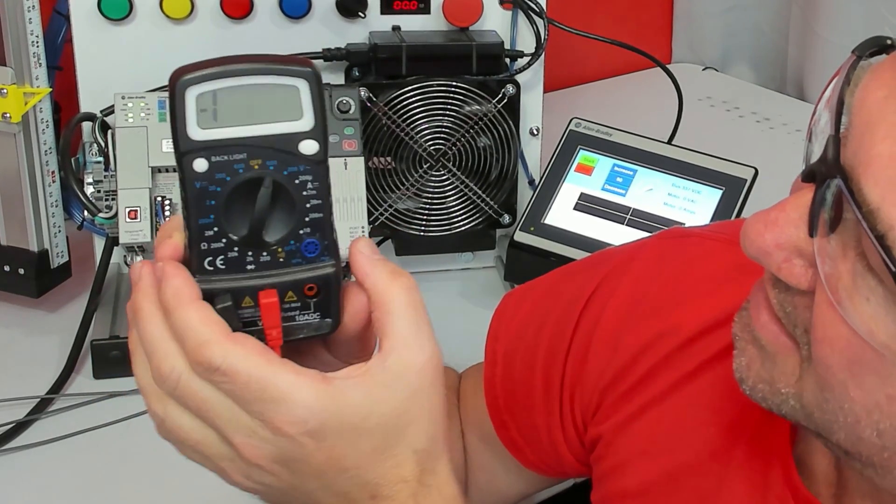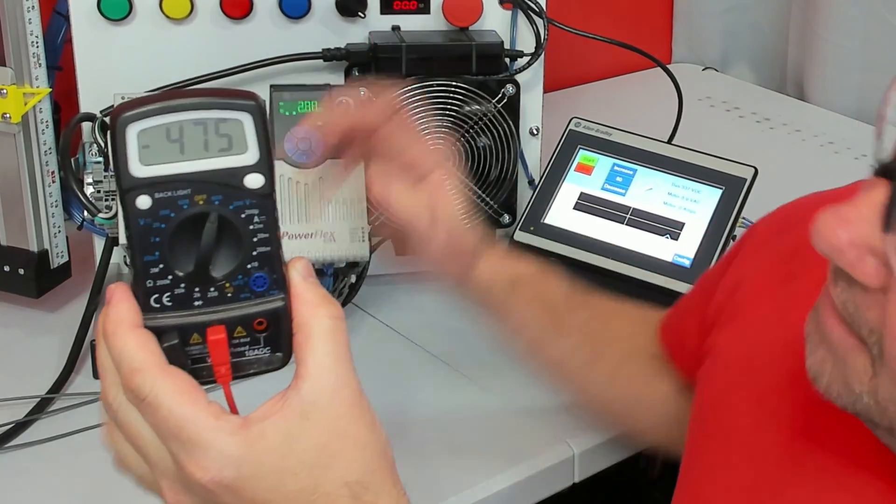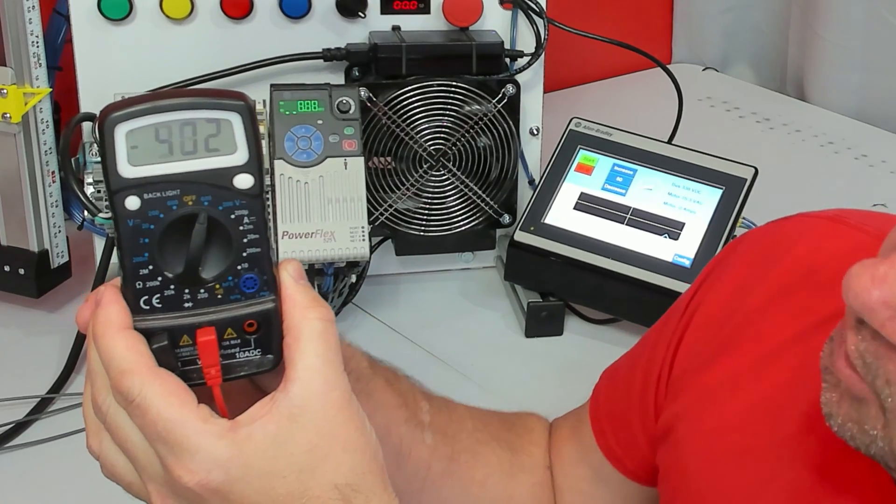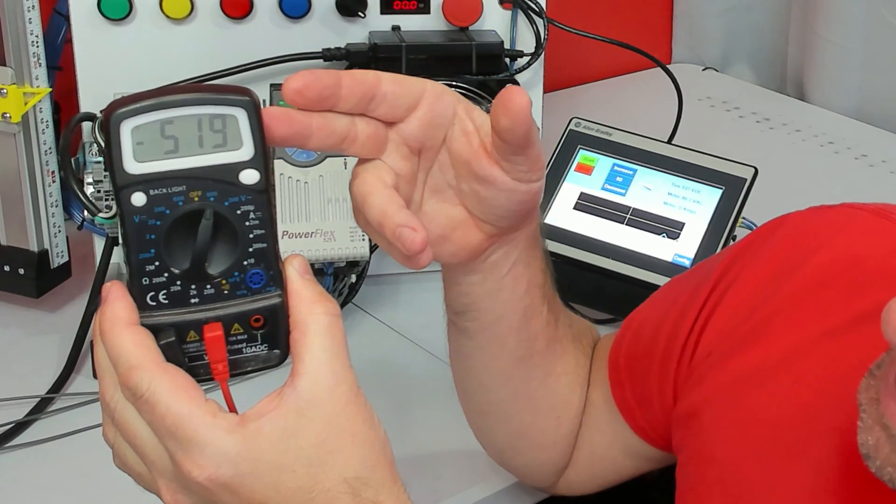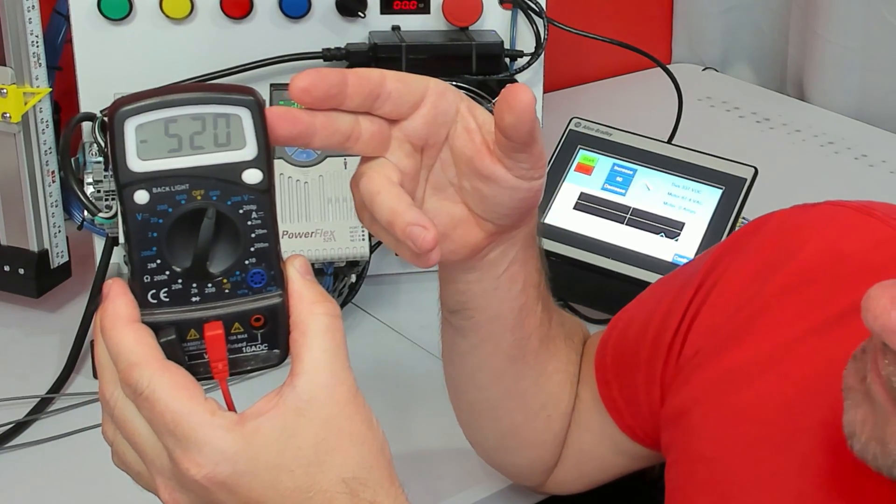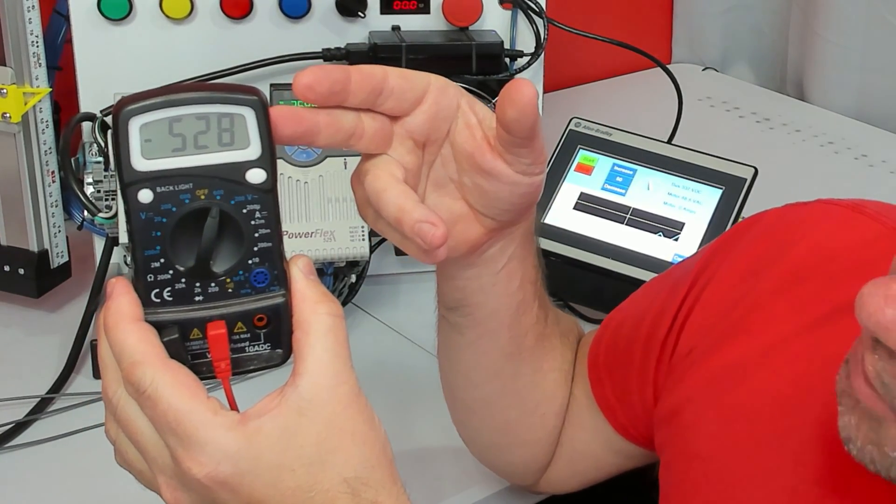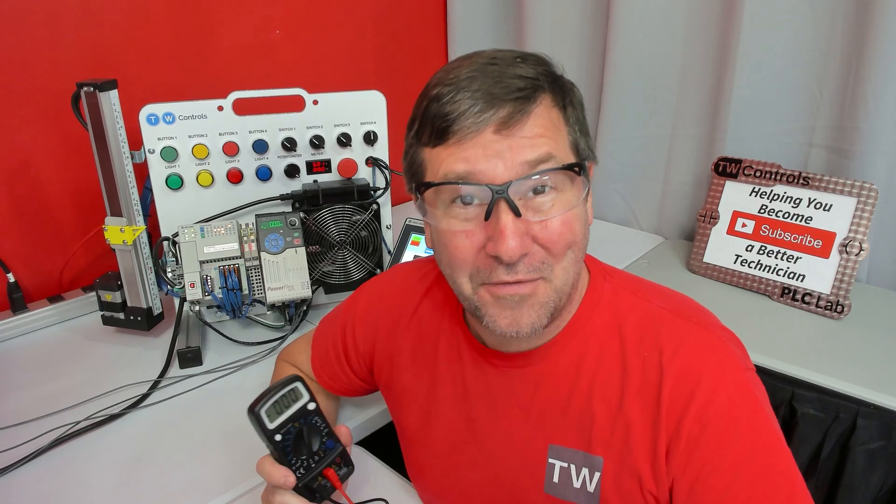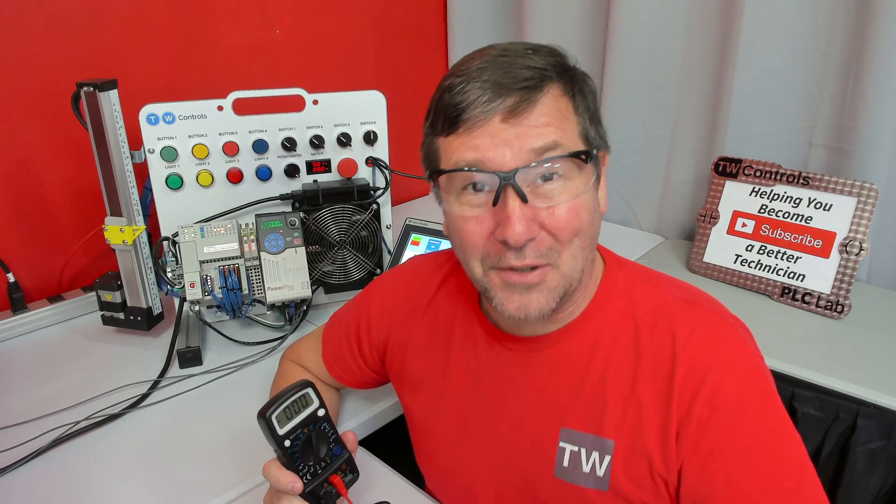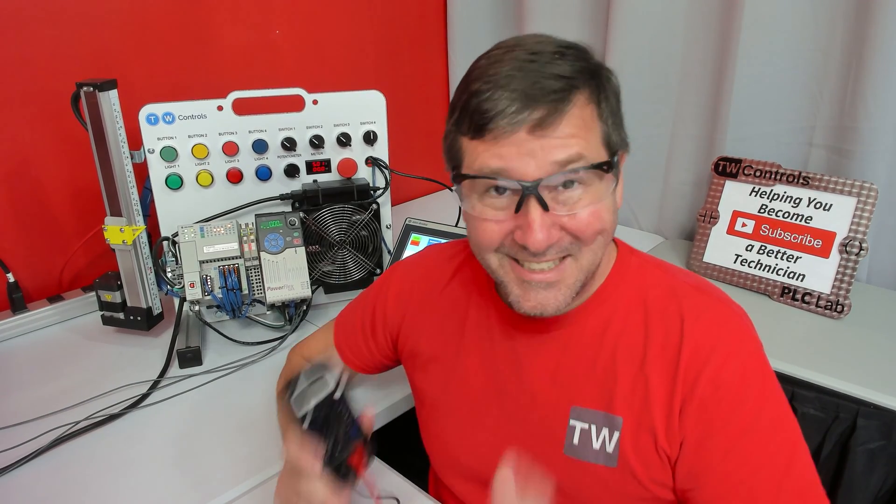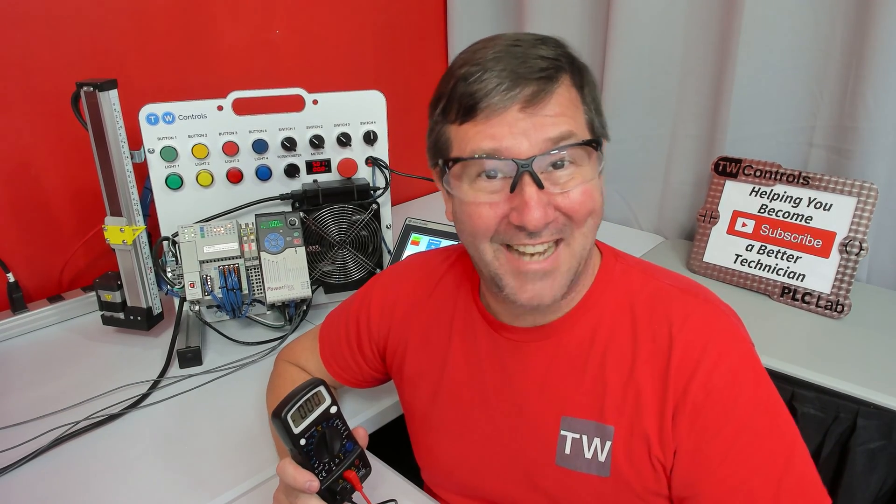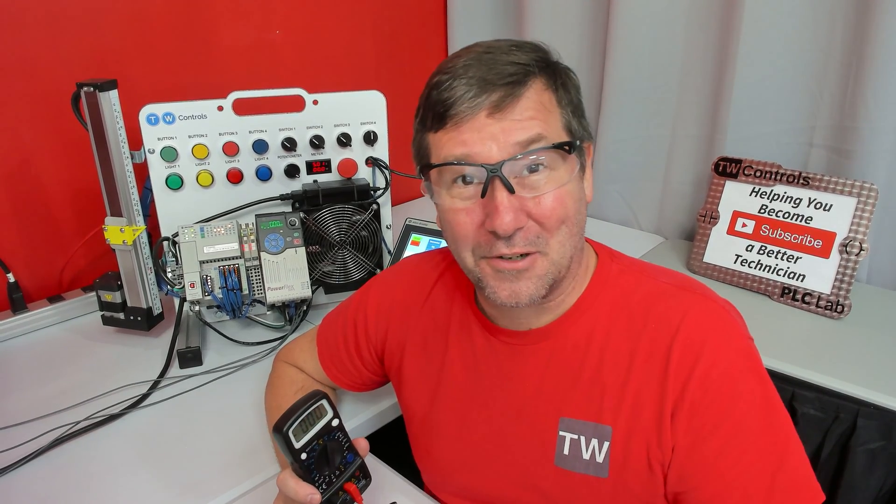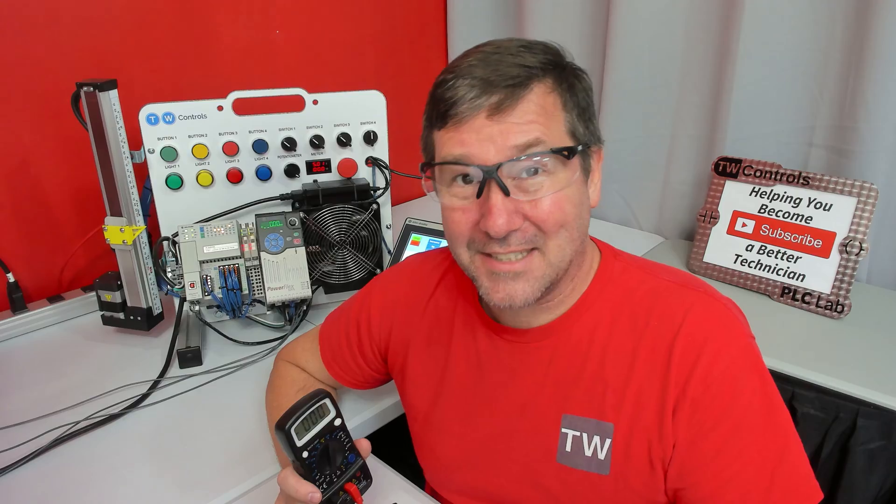I'm going to go with 600 volts. And when we start our motor, we got negative 530 volts. How can you have that on a 240 volt motor? And this is an exercise that we go through in our training class.